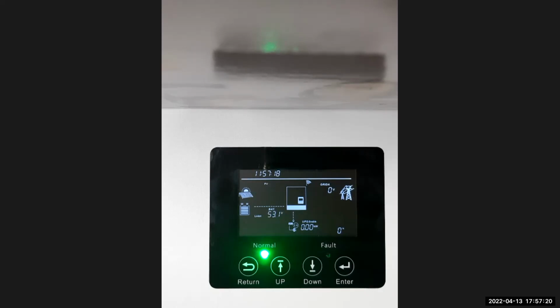Is there a changeover time when load transfers from mains to batteries? That's correct, it is. You're looking at between 10 and 20 milliseconds changeover at the moment. That's for all inverters. That's why our output is called an EPS. All inverters have a switch over time. Ours is between 10 and 20 milliseconds, usually closer to 10. So in 90% of the cases, you won't realize the inverter has switched from mains to batteries. But yes, we have a switch over time.